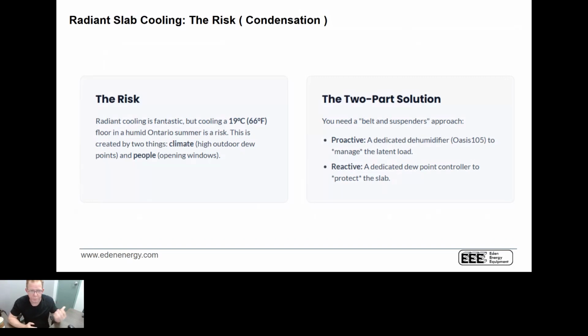Now, the fun part is the radiant slab cooling side of it. Radiant slab cooling makes me nervous every single day I talk about it, right? The risk in a radiant slab system is the condensation. Doing radiant cooling is not like doing cooling with an air handler or a low temperature convector. We need to be aware of the risk. Radiant cooling is fantastic, but the challenge we've got to be aware of is the humidity, right?